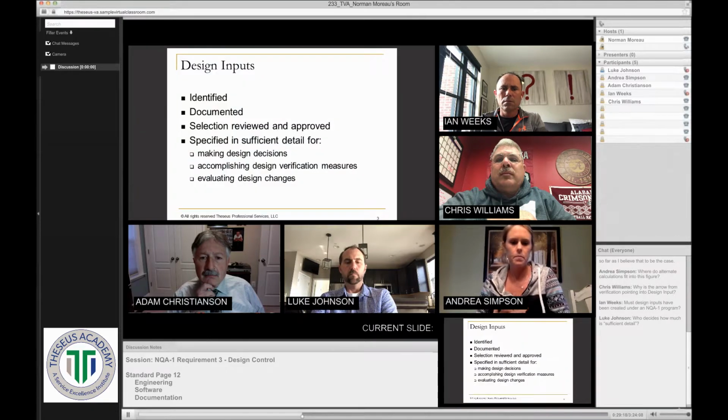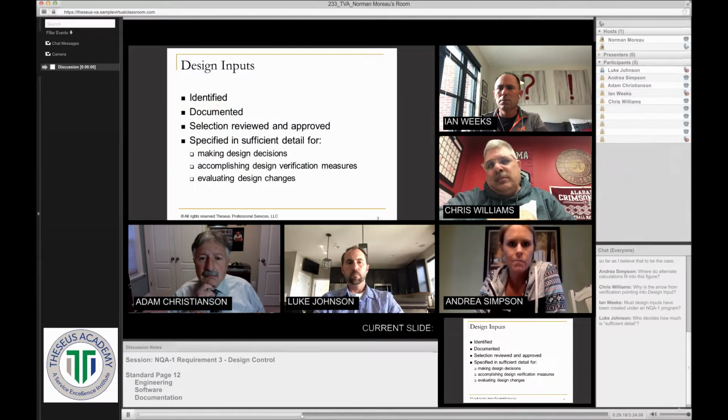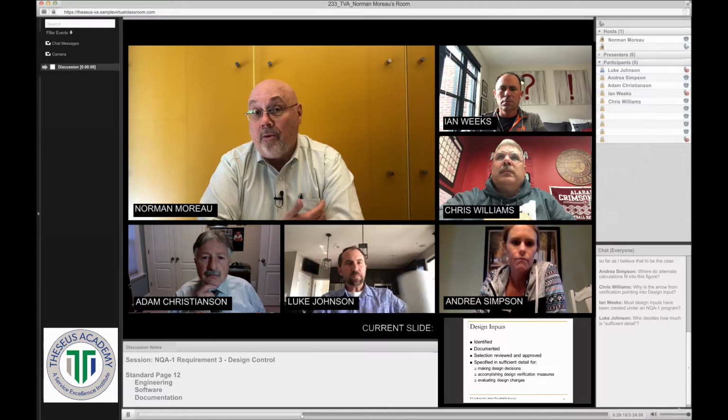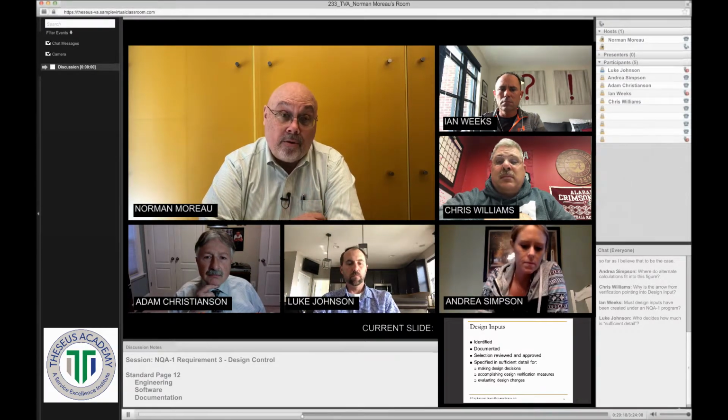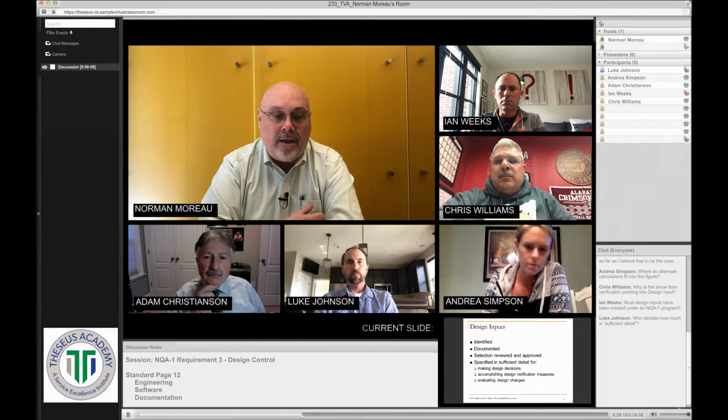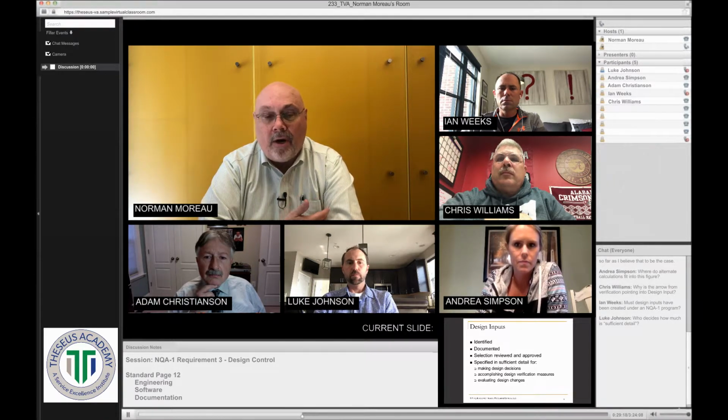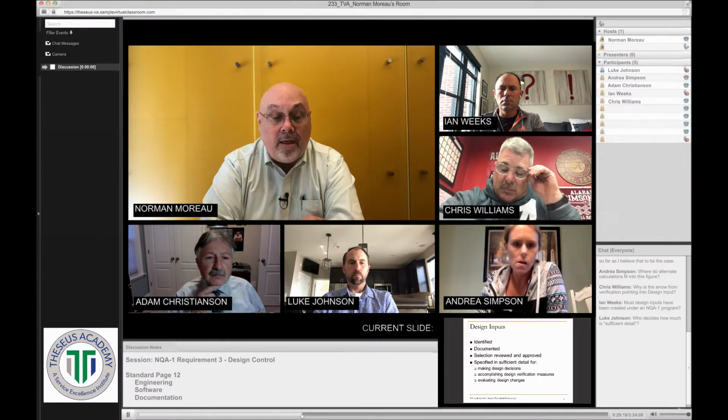The next slide is about design inputs, and there's very specific requirements. Identified, documented. How did we select them? Someone has to review and approve those inputs, and simply say, these are the inputs.